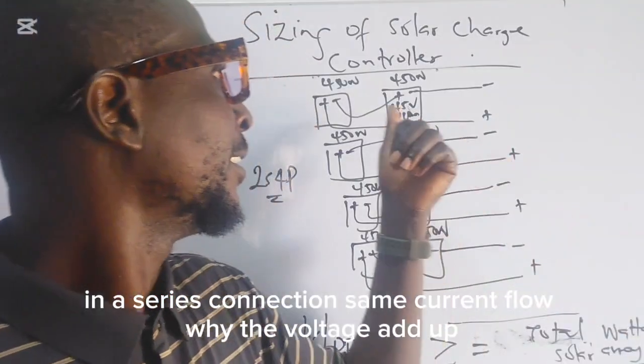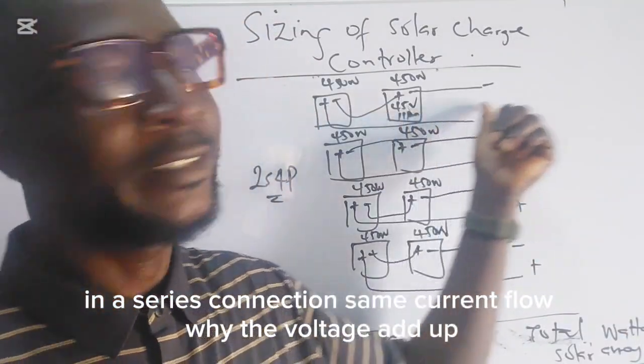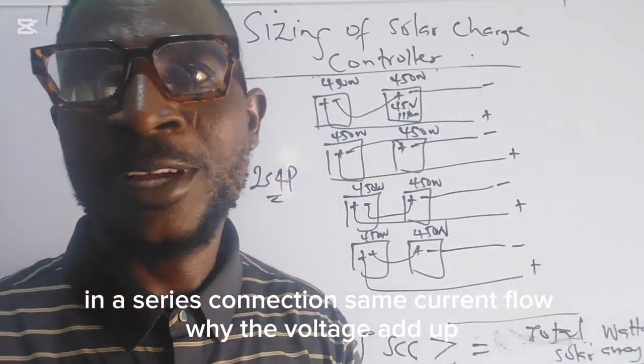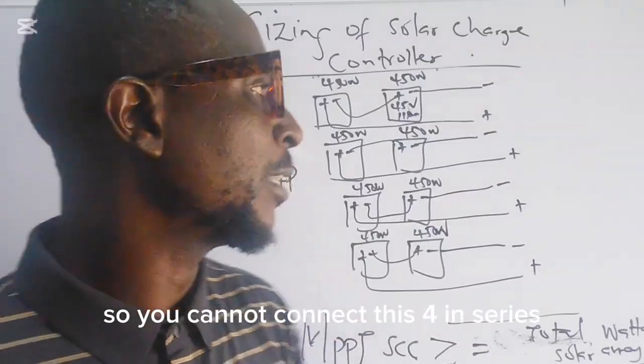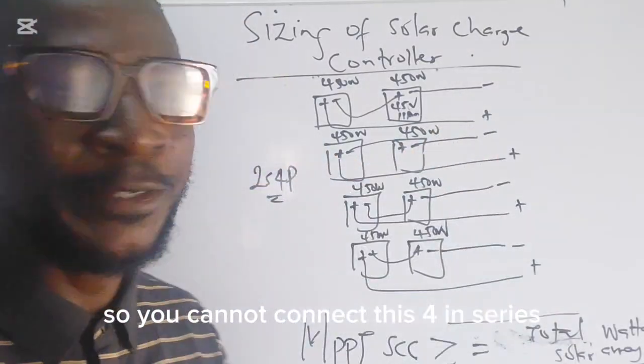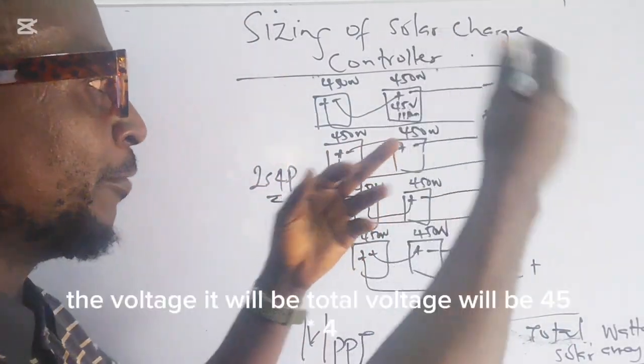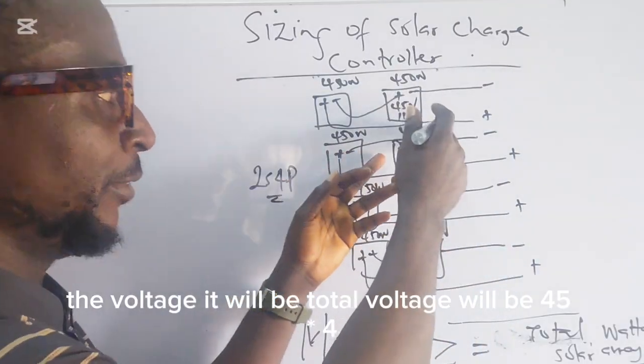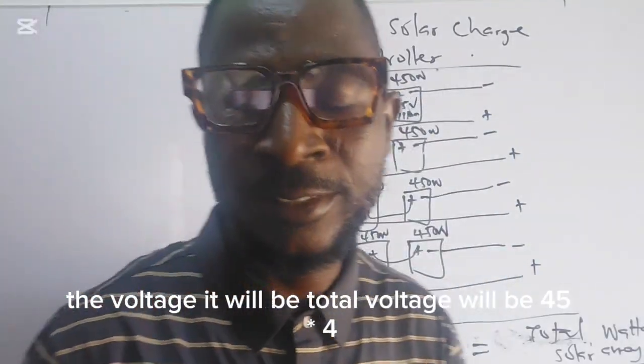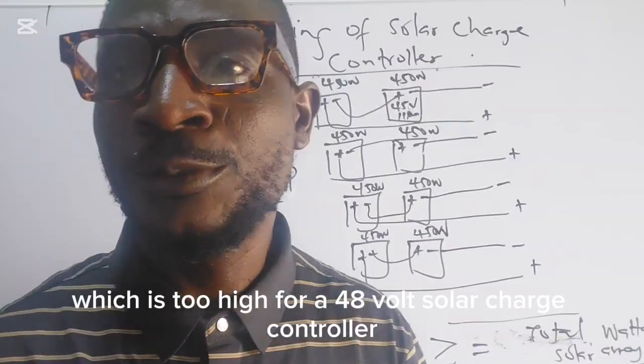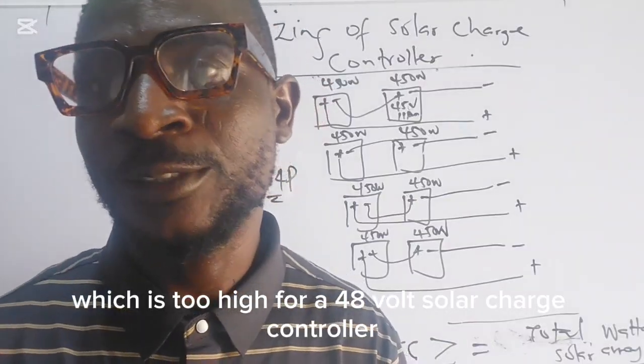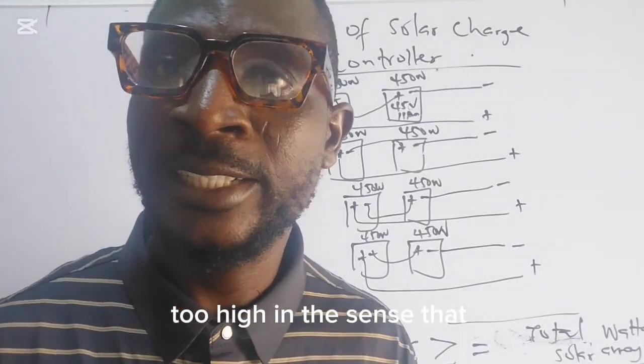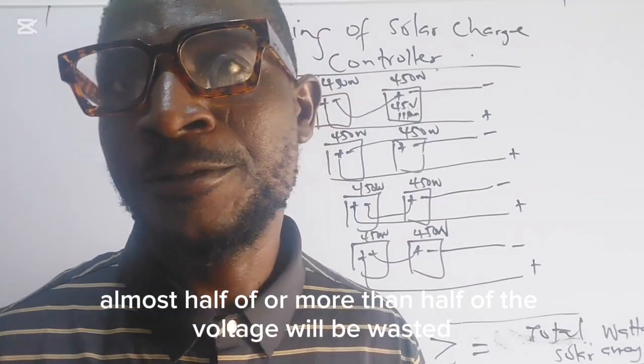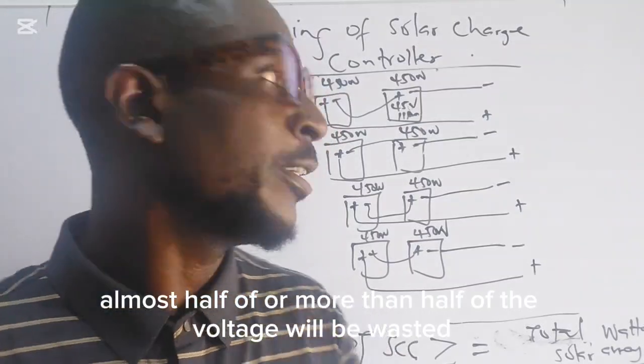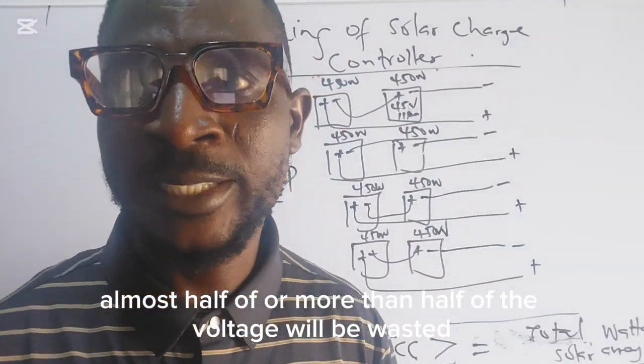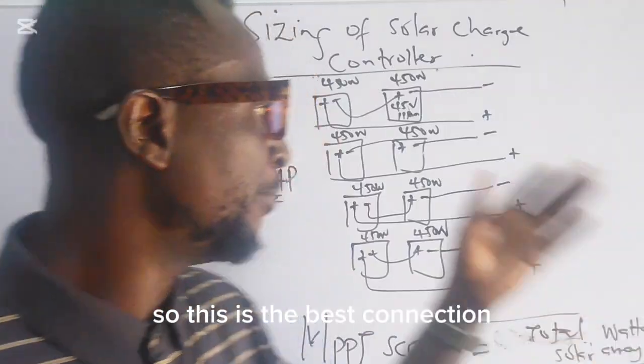You know, in a series connection, the same current flows while the voltages add up. So you cannot connect these 4 in series. When you connect these 4 in series, the total voltage will be 45 times 4, which is too high for a 48 volt solar charge controller. Too high in the sense that almost half or more than half of the voltage will be wasted. So this is the best connection.